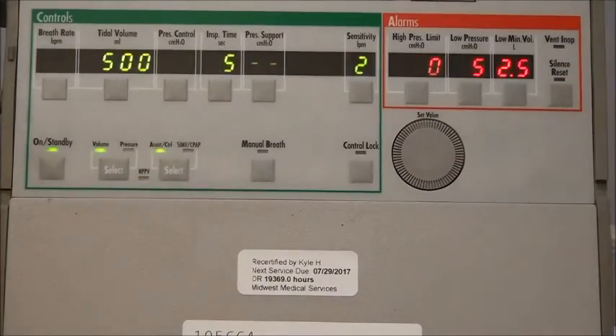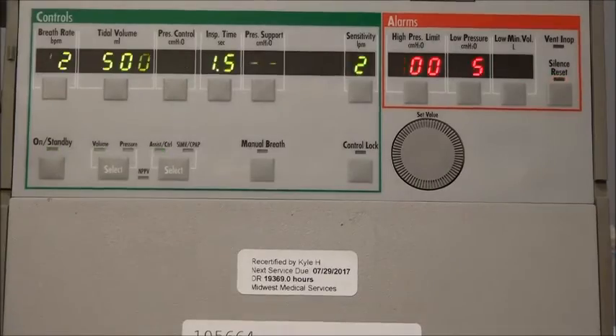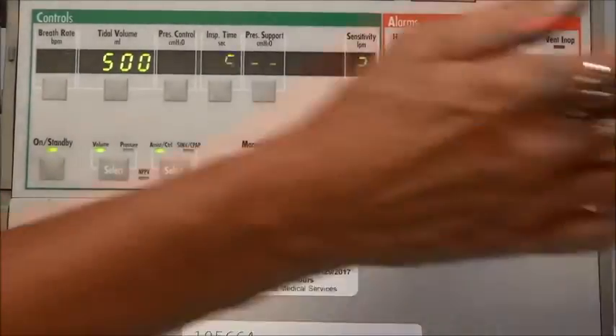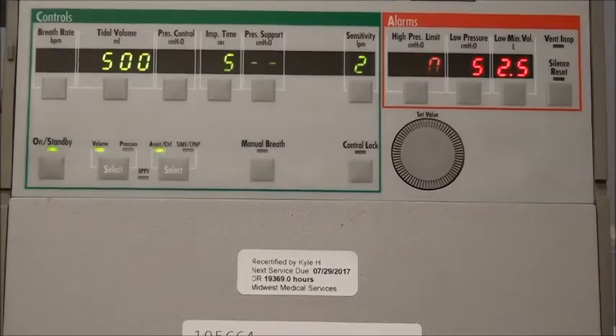Now right now I'm getting a low minute volume alarm, so I'm going to push the reset button. I'm going to check on my circuit and make sure everything's connected correctly. Then I'm going to reset it. I found my problem, everything's working fine.